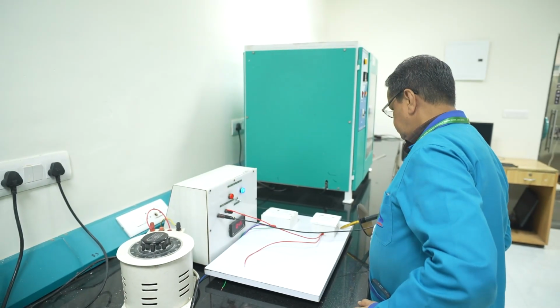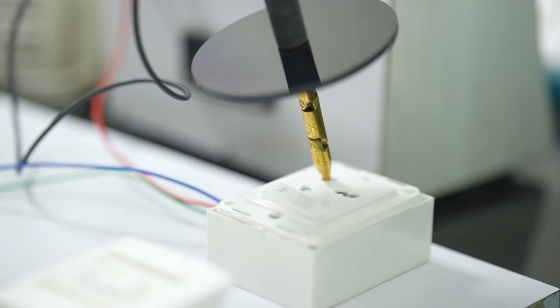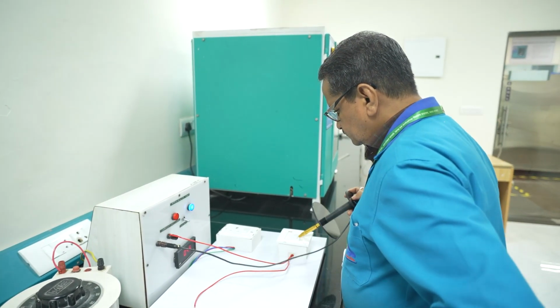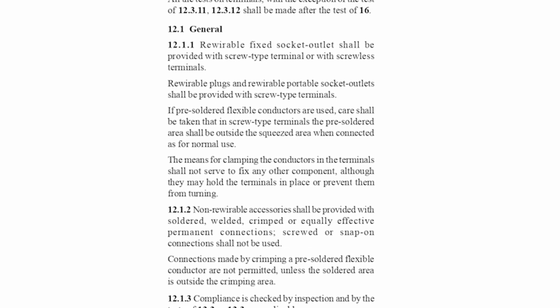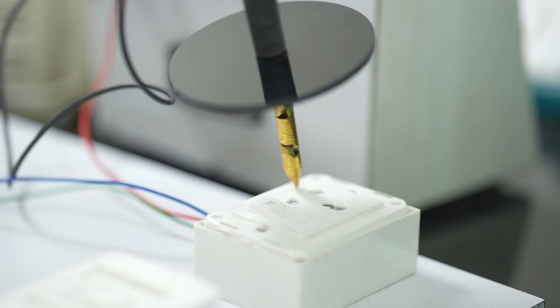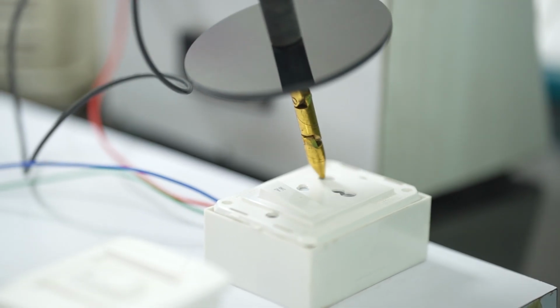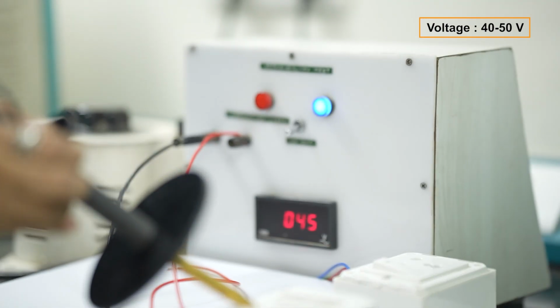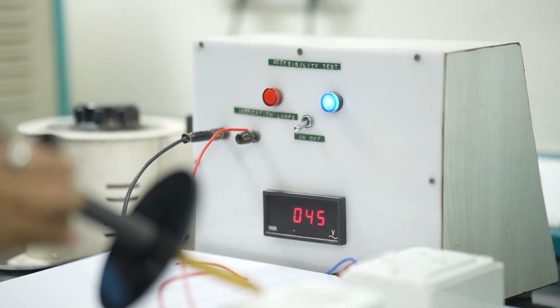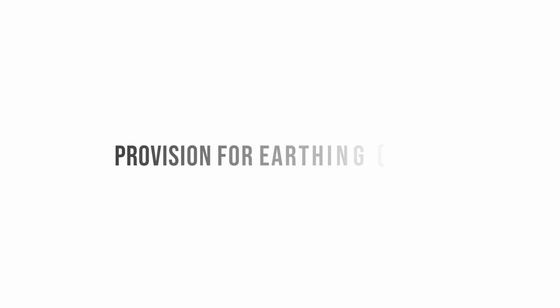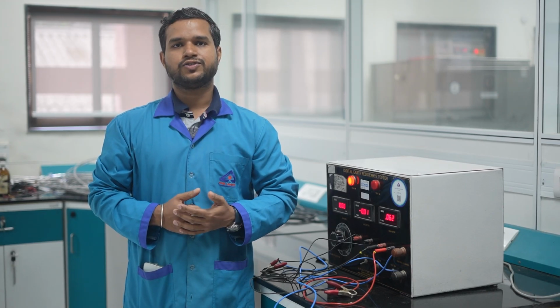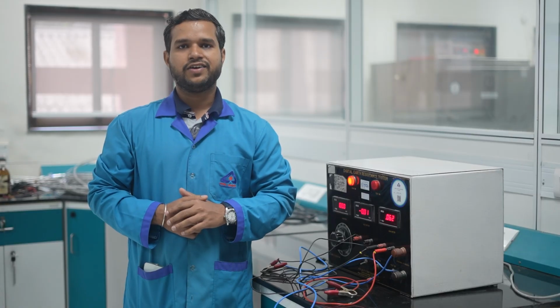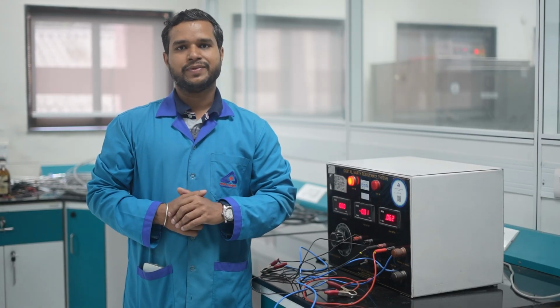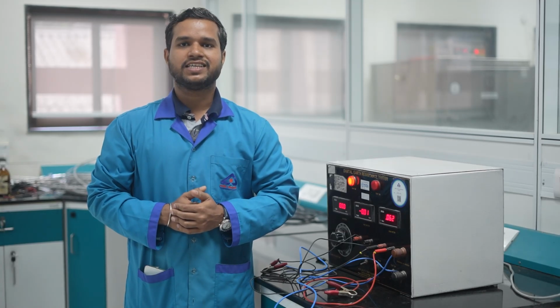Compliance is verified through inspection and by conducting the test. The specimen is mounted as in normal use and fitted with conductors per clause 12. The standard test finger per IS 1401 is applied in all possible positions with a 40 to 50 volt electrical indicator to detect contact with live parts. Provision for earthing. Clause 11. To ensure effective grounding in the event of insulation failure, the earthing terminal is verified for presence and its continuity is measured. This guarantees user safety against electric faults.